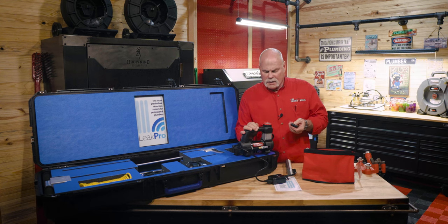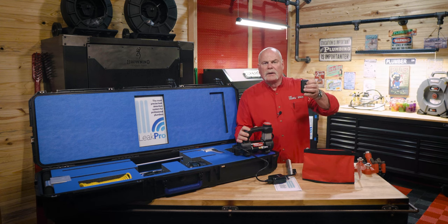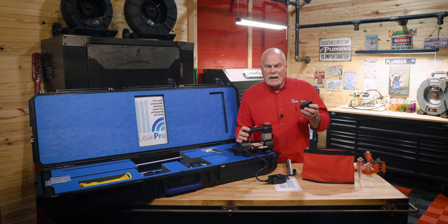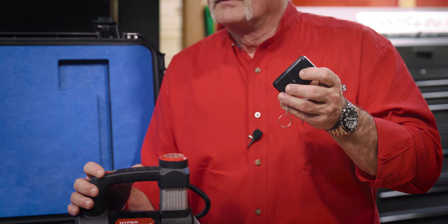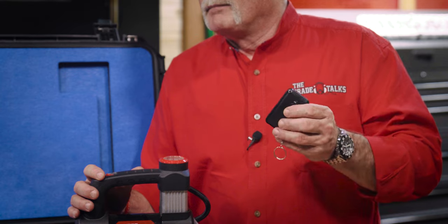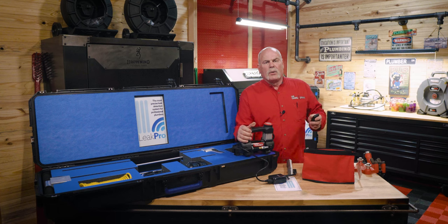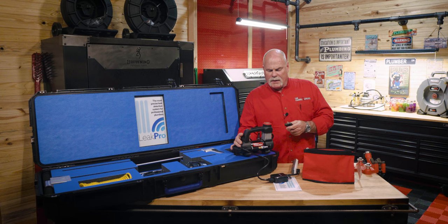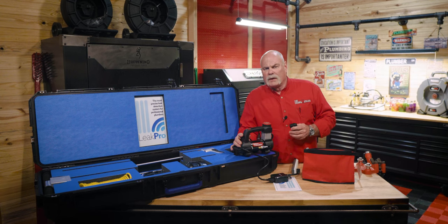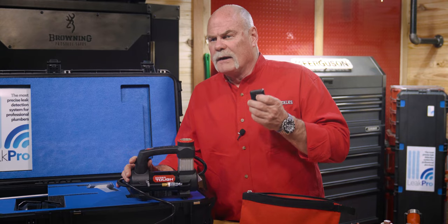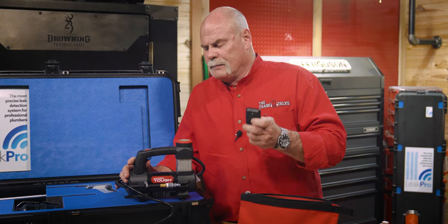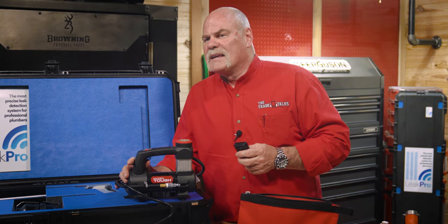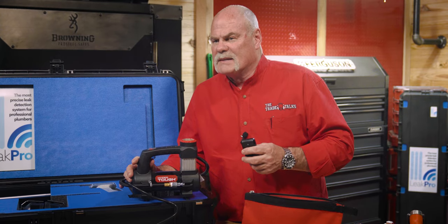Look at your gauge, make sure your unit's on. Know what your gauge is saying. Here's what's neat about this. If you're going through the house and maybe you've got a job that leaks down fairly quick, well, you can look at your gauge and say, okay, it takes 15 seconds to get it up to 10 PSI.